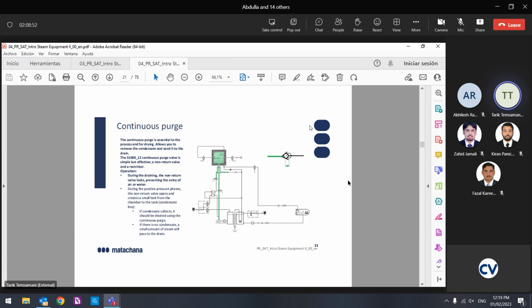We'll see if it's clear or not after checking that. But it's easy. What is the purpose of this purge actually? The purge is to remove the condensate. Once you put the steam here, this is condensate. To remove this condensate, the water from the chamber. But in the case of the chamber, it is only at the moments of steam injection. In the case of the jacket, always.